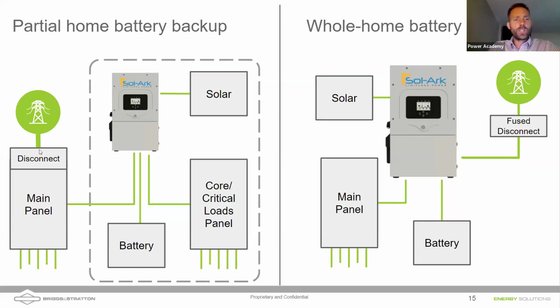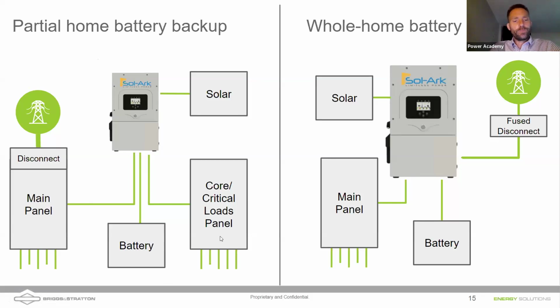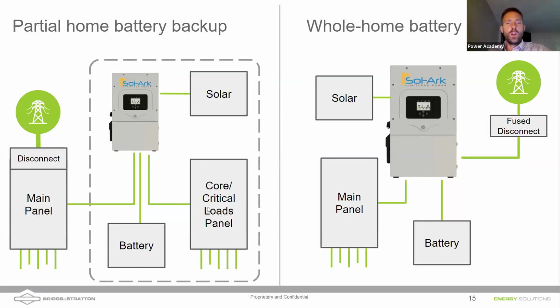So in a grid down situation, all of the loads that are in the main load panel are not backed up. On the other side, on the critical loads side, you would feed a sub panel out of the inverter, and all the loads that you've moved over into the critical loads panel would be backed up in a grid down situation. So you could feed that solar into the inverter, and you could feed a battery into the inverter.